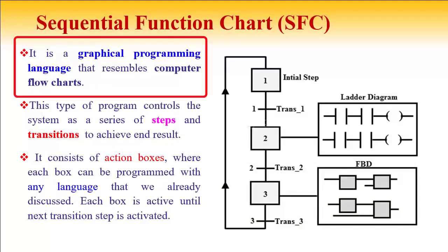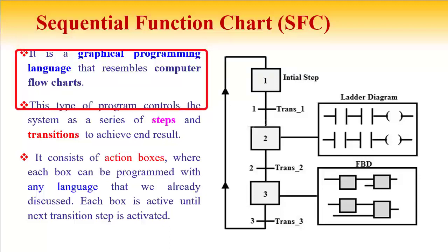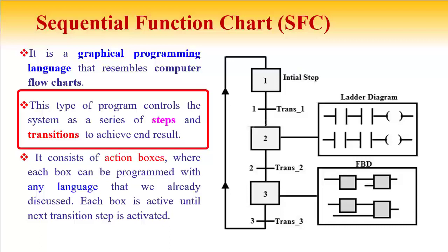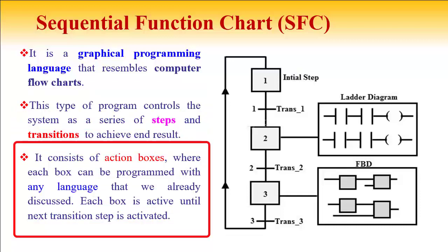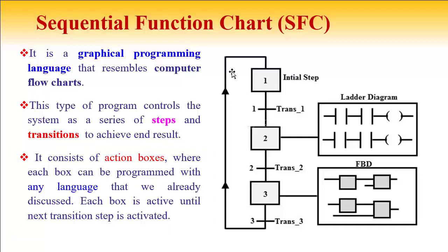Next is Sequential Function Chart (SFC). It is a graphical programming language that resembles a computer flowchart. This type of program controls the system as a series of steps and transitions to achieve end results. It consists of action boxes where each box can be programmed using any of the languages already discussed. Each box is active until the next transition step is activated.